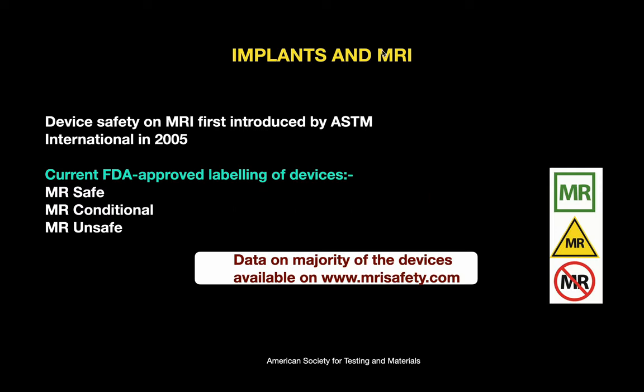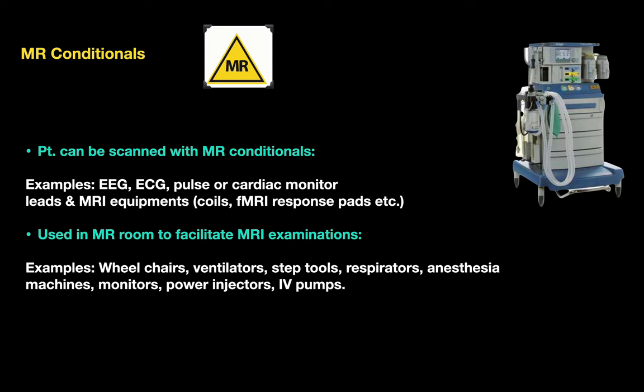Device safety in MRI was first introduced by ASTM (American Society for Testing and Materials) in 2005. Current FDA-approved labeling for devices are: MR Safe (green), MR Conditional (yellow), and MR Unsafe (red). Data on the majority of devices are available at www.mrisafety.com. MR Conditionals include EEG, ECG, pulse or cardiac monitor leads, and MRI equipment like coils and functional MRI response pads.